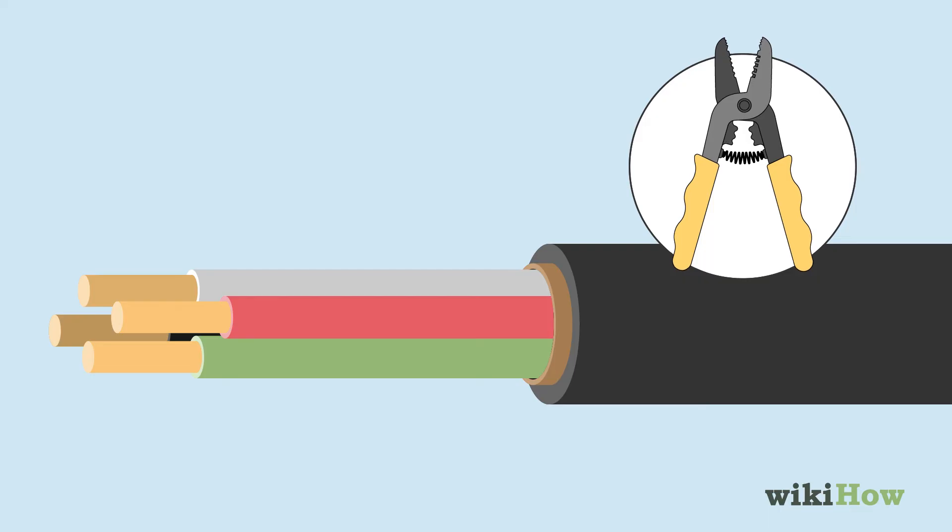Strip the outer coating off of the last 1 to 2 feet, 30 to 61 centimeters, of the end of the cable that will attach to the circuit box. Then strip half an inch, 1.3 centimeters, of insulation off of the ends of each of the wires.